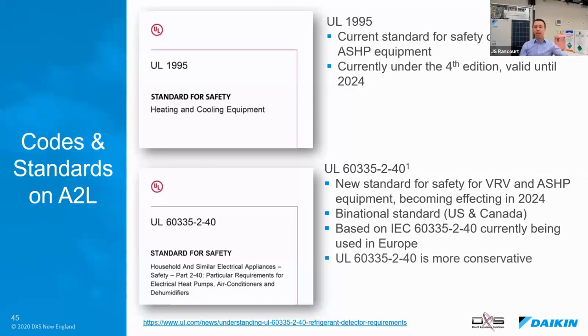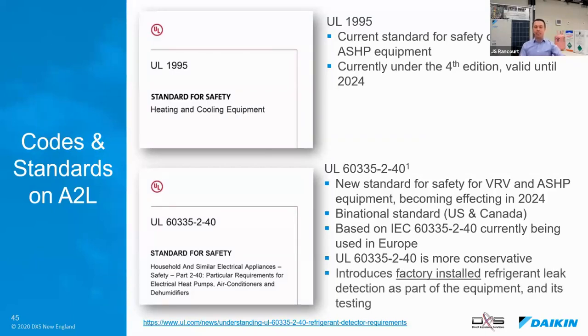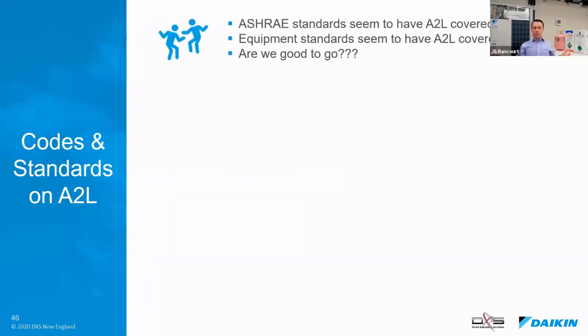The UL version in the US is a lot more conservative. So we're a lot more conservative in the US on flammability and safety, which is a good thing. So that's UL 60335. It's already available for manufacturers to start doing R&D on their equipment on this. But the big thing that this UL standard now does is it introduces factory installed refrigerant leak detection as part of the equipment and as part of the testing. So it seems as though the ASHRAE standards have A2L covered, the equipment standards have A2L covered, so aren't we good to go? The answer is no.